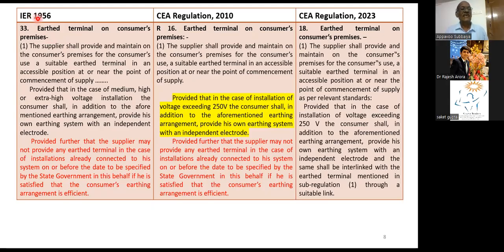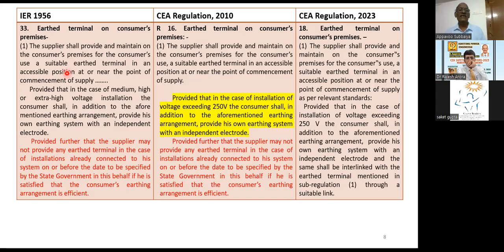See, you can see regulation 1956, that is, earthing at consumer premises. What it says is that the supplier shall provide and maintain an earth terminal at the consumer premises for the use of consumers. So that means the supplier should provide, as in the previous slide, PME, protective multiple earthing. That particular conductor should be given to the consumer. The consumer in turn has to connect his protective conductor, his PE conductor, to this earth neutral terminal. They call it earth neutral. So here there is one provision where the supplier need not provide it if they are satisfied and the state government is satisfied. It fixes the accountability on the state government.